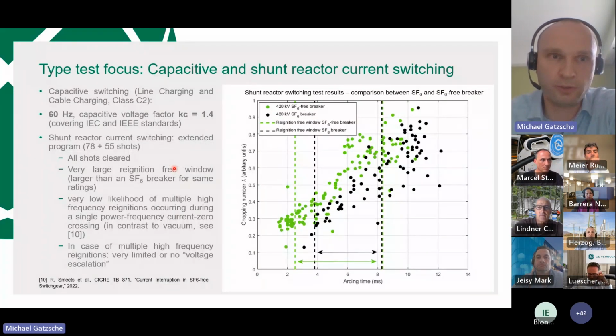One very important focus point is capacitive and shunt reactor switching. For capacitive, we did line and cable charging according to class C2, for 60 Hertz and with a capacitive voltage factor of 1.4. We think that's a really good rating covering a lot of applications. Then also the shunt reactor switching, where we did an extended program with all shots cleared. Even there, when we compare with our SF6 reference, we have a very large reignition-free window that is even larger than for the SF6 breaker, and a very low likelihood of multiple high-frequency reignitions.